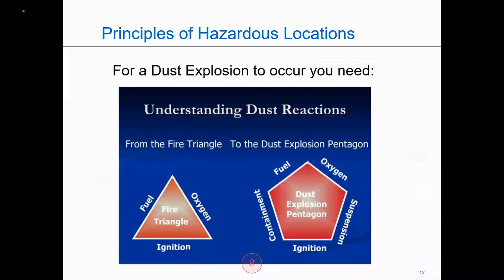Now, when it comes to combustible dust, the combustion triangle turns into the explosive pentagon. We still need to have our fuel. In this case, it's going to be the combustible dust. We still need to have our oxidizer. We also need to have our ignition source, but now we're going to add suspension, the dust in suspension and in containment.